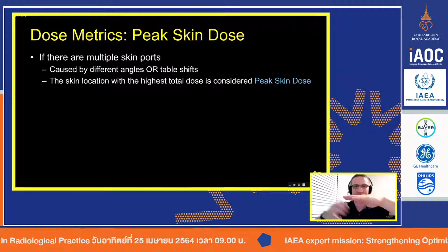So that cumulative air Kerma value that's listed, that's the total for the entire exam. But now if you look at this one, there's 1, 2, 3, maybe 4, 5, 6, who knows, maybe 7 or 8 different angulations and movements. We need to understand what the actual peak skin dose is, not the total skin dose. Because if you take 10 milligray of dose over here and 100 milligray of dose over here and 50 milligray of dose over here, if you sum it all up, it says here 451 milligray.